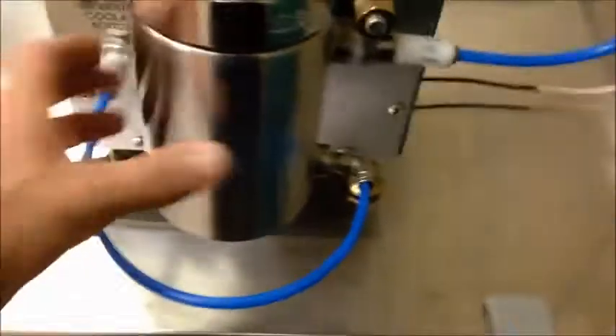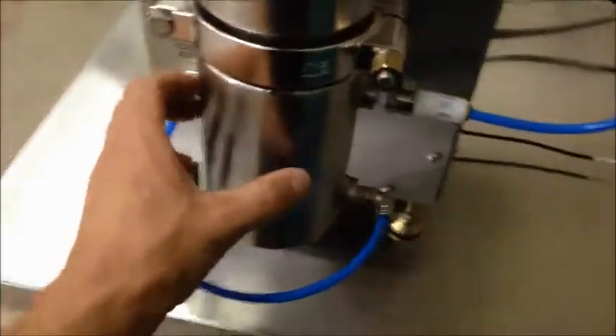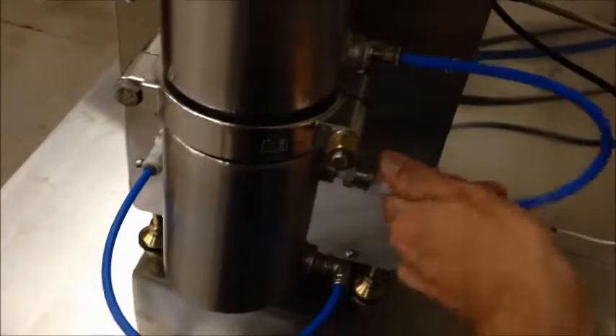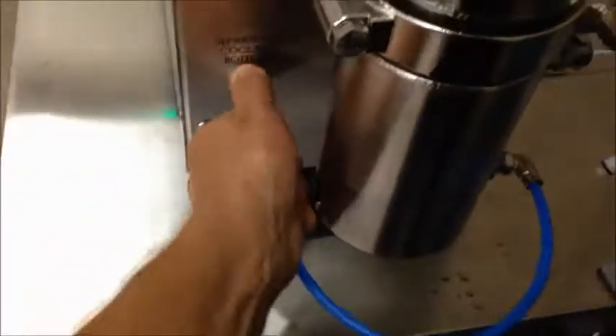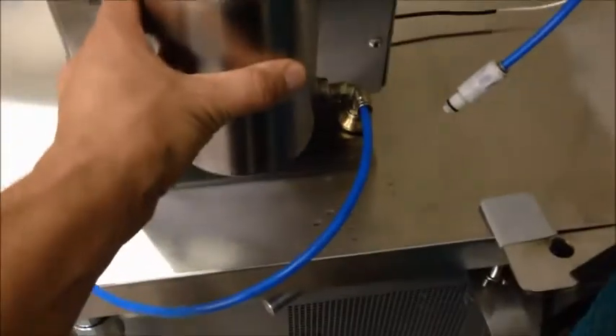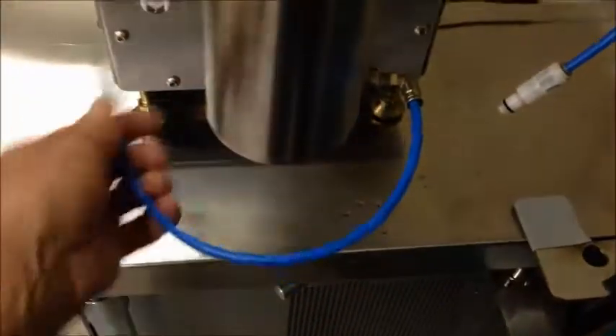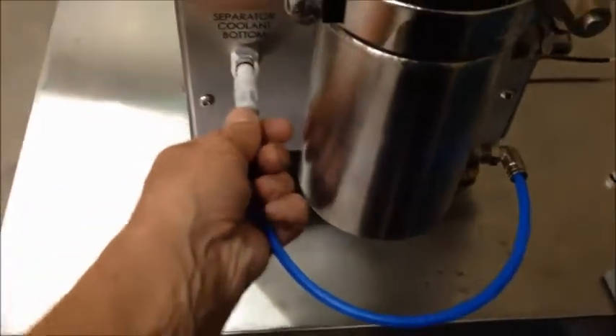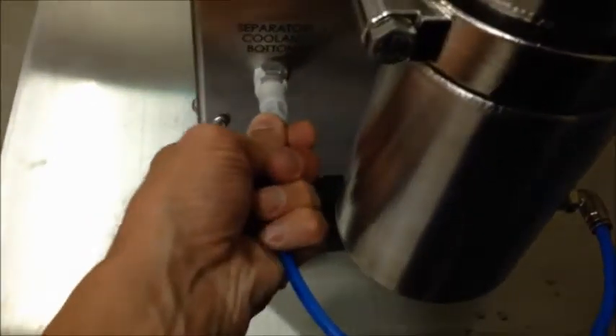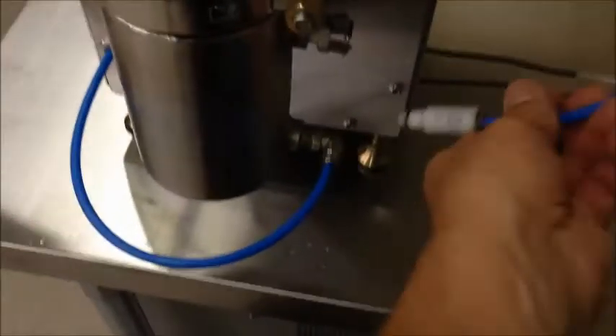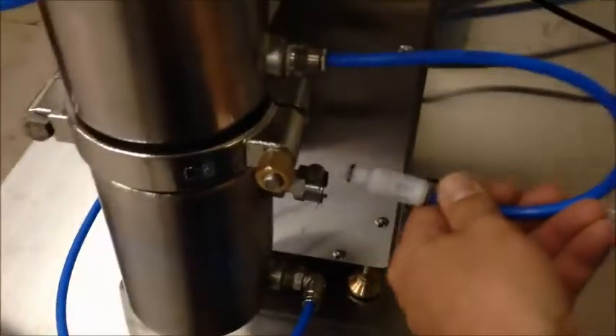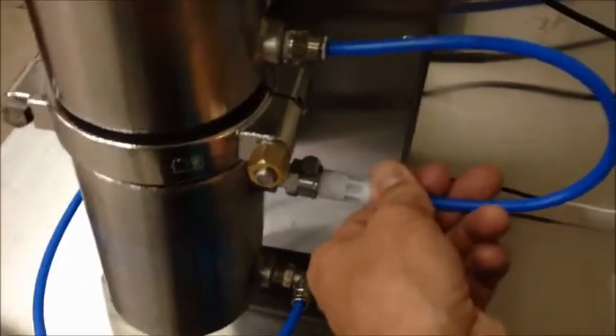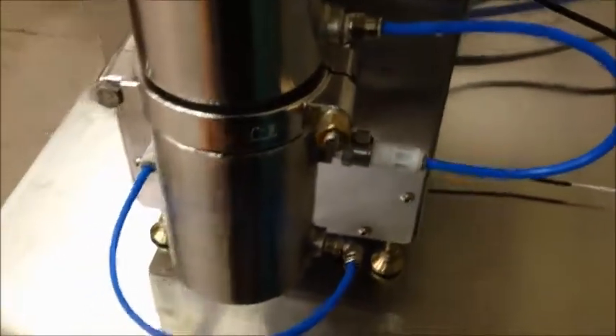These blue lines here, so you can actually take your separator cup away from the system, carry it somewhere to take the oil out, actually pop off right here and right here. And then you can actually pick this up and take it where you need it. And when you come back, ensure that you put these all the way back into the clip. If not, your separator will freeze over during the extraction process. There you go, it's all connected back together.